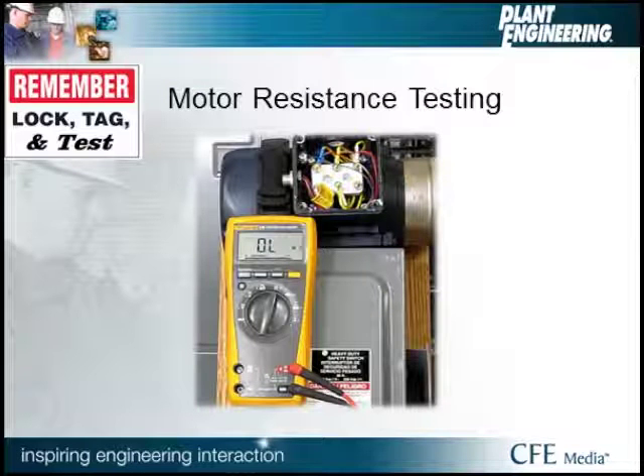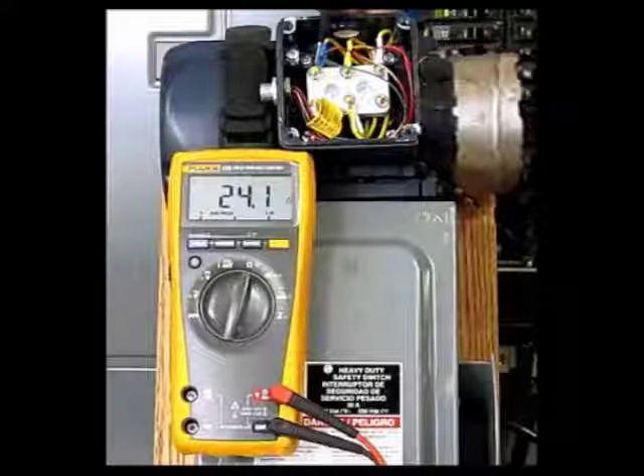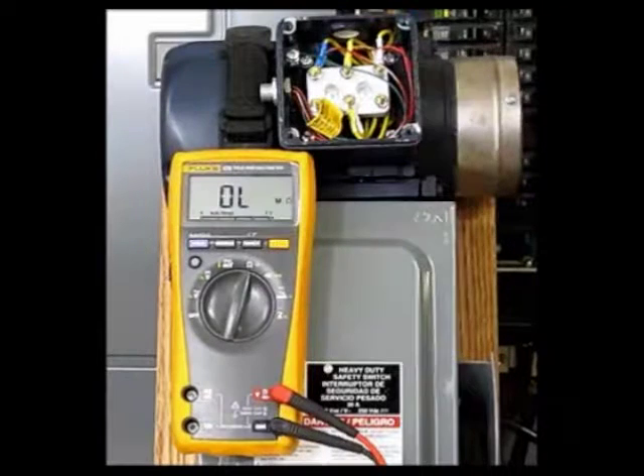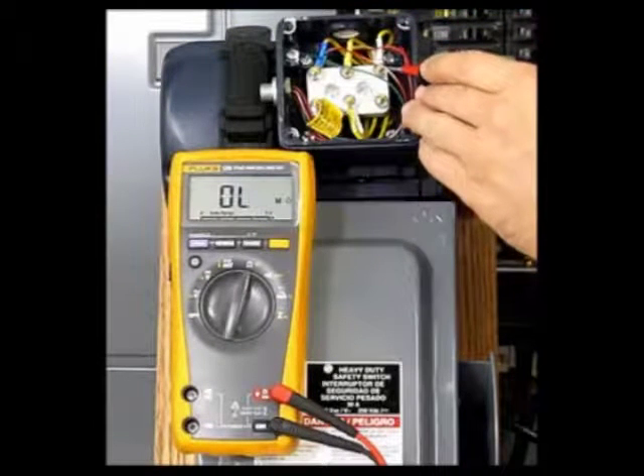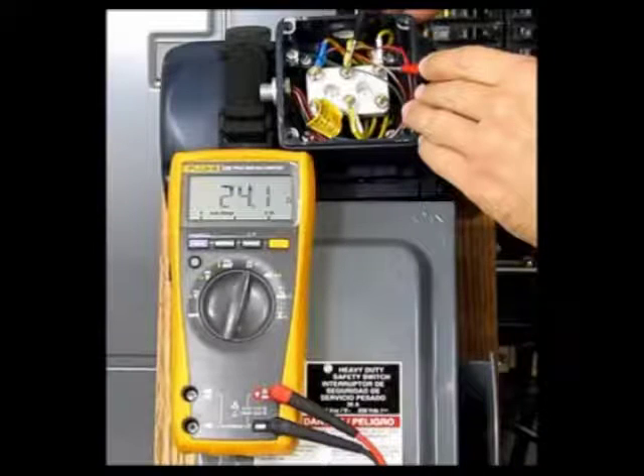Our first test is for motor resistance testing. Remember, continuity testing should be done with the system de-energized, locked and tagged out, and proven that it's de-energized with a voltage test. This is also known as a live, dead, live test. In this video, we're doing a resistance test on the windings of a three-phase motor. This can be done to diagnose any problems we might be experiencing with the motor.